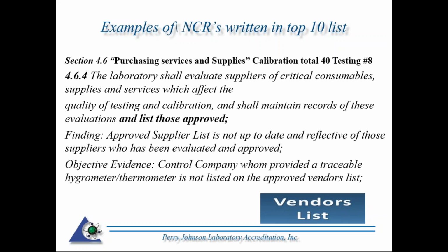A record of those that was inspected and approved upon receipt should be maintained. One thing that comes to mind, I'm talking about calibration, this could be a testing lab too. When you send an instrument in to be calibrated and it comes back, what needs to be inspected is the actual report. Did you get, let's say for example, you needed the accredited report.